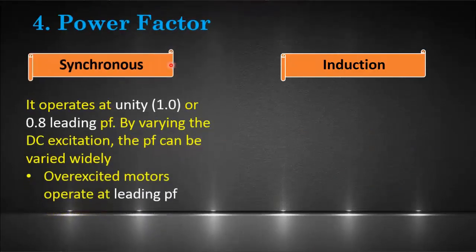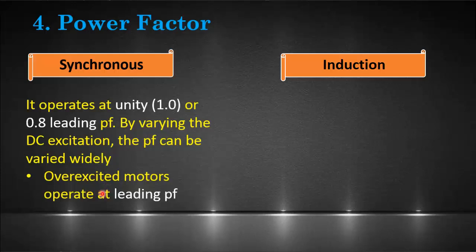Another difference is based on power factor — the angle between current and voltage. The synchronous motor normally operates at unity or 0.8 leading power factor, and we can control its power factor from lagging to leading by varying the DC excitation. Over-excited synchronous motors operate at leading power factor and are used for power factor correction, whereas the induction motor only operates at a lagging power factor.